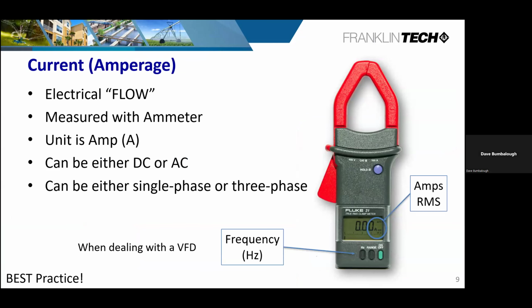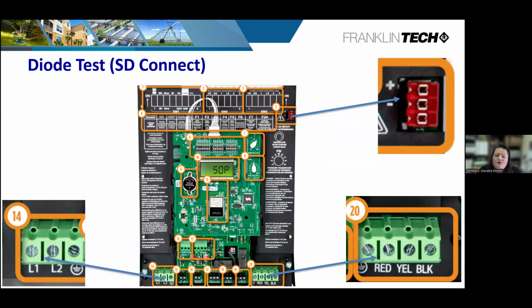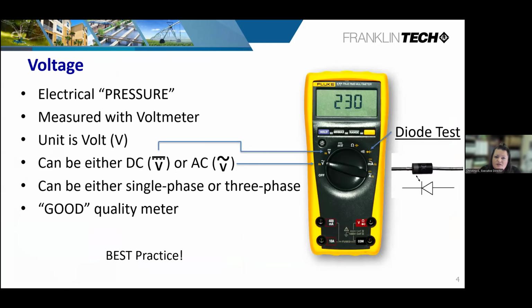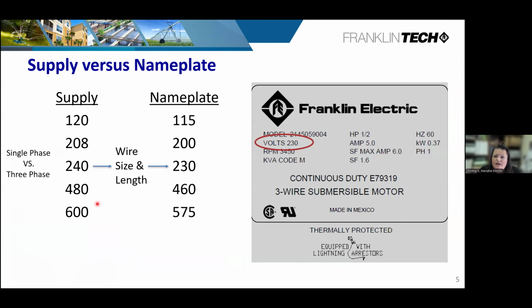So, Dave, yes, sorry. To go back to when you were speaking about the power companies delivering higher voltages than what the motors are designed to take in, Mark from Roar Drilling had a comment that he ran into a resting voltage at 9 a.m. of 249. Then at 8 p.m., the Pumptec-Plus was faulting out on over voltage. And essentially, the power company had him bypass the Pumptec until they could get it resolved. So the voltage and the supplies are affecting these pump systems from operating as they were designed. That is correct.